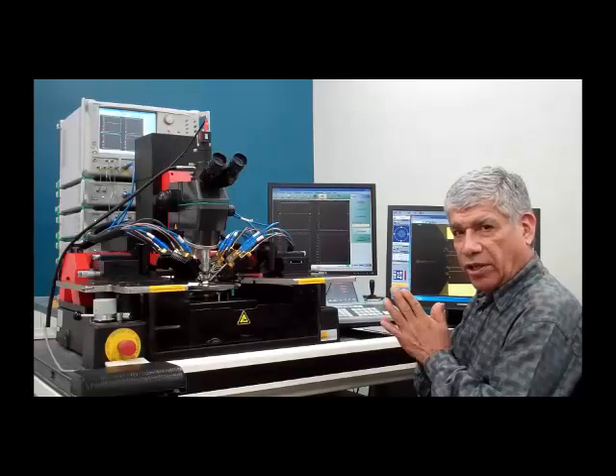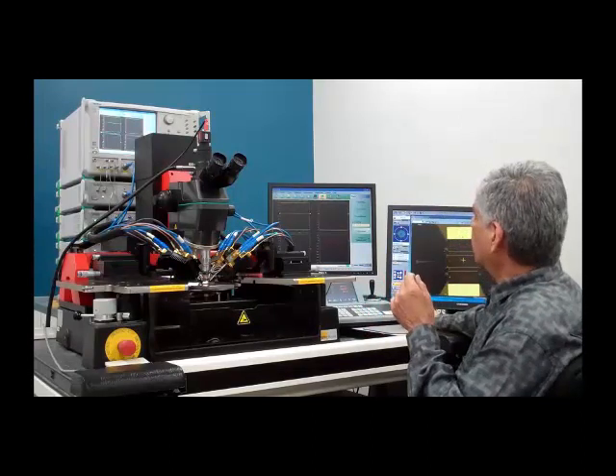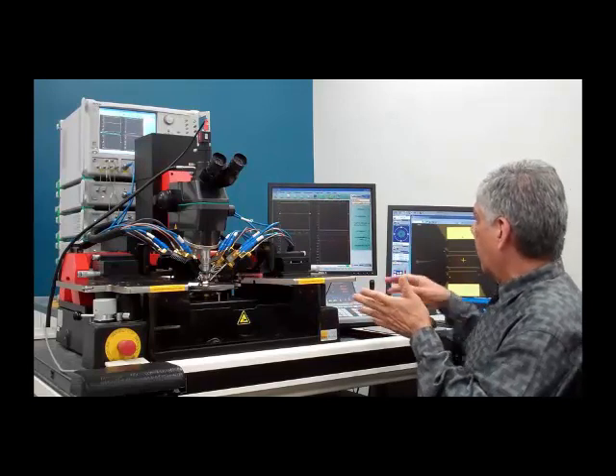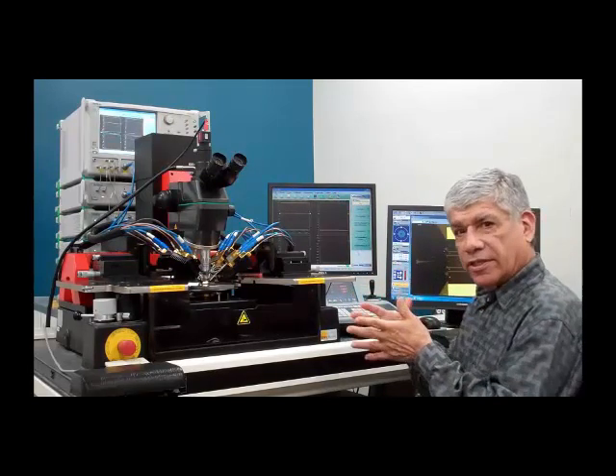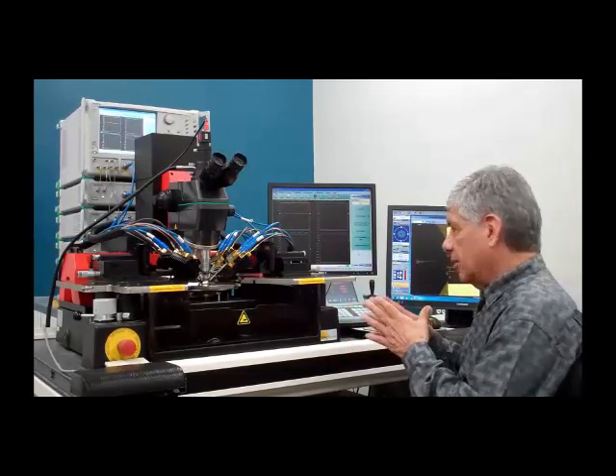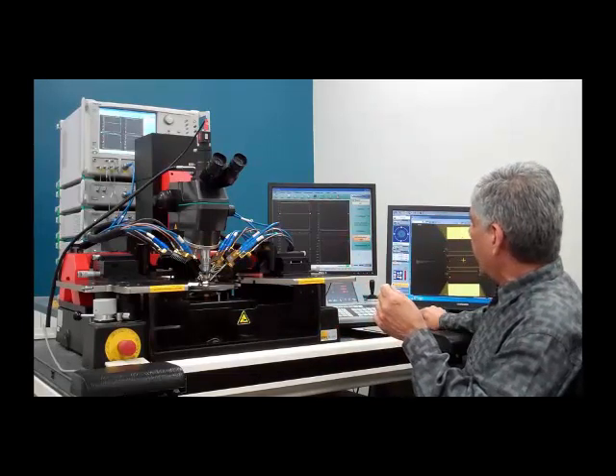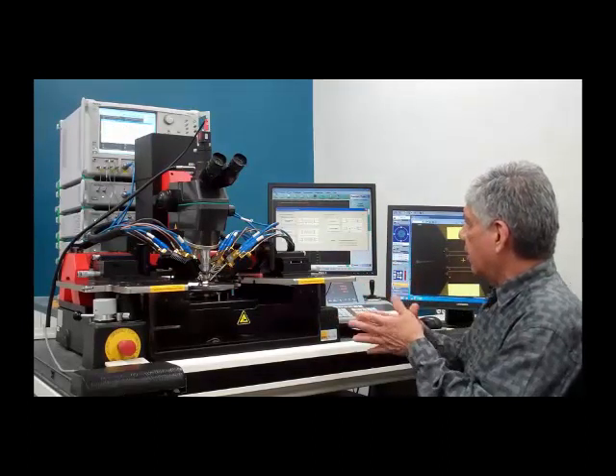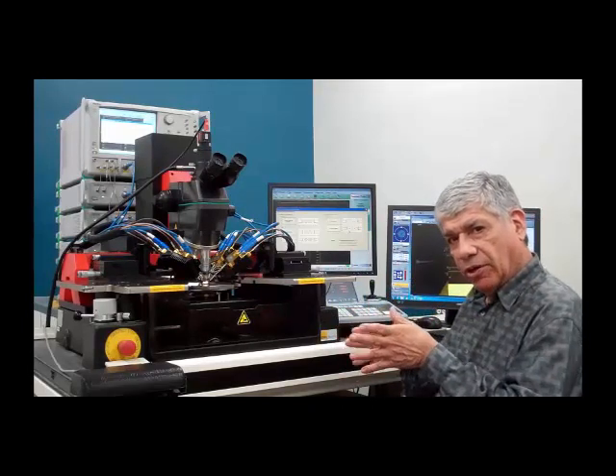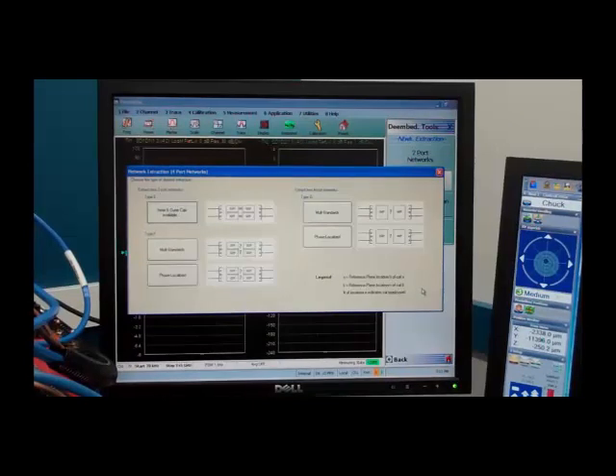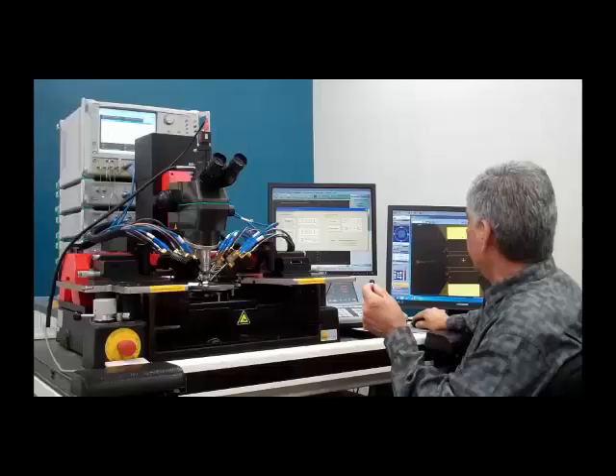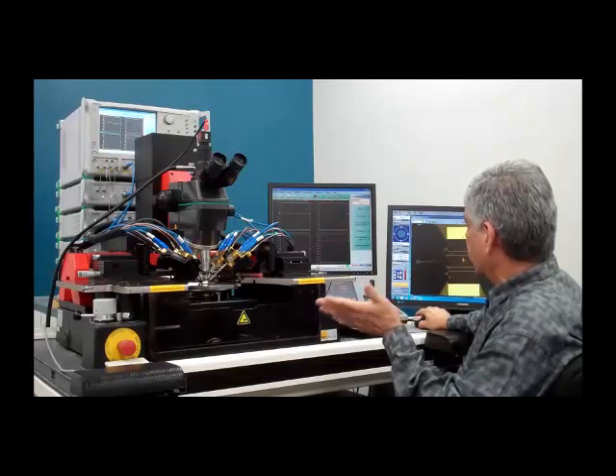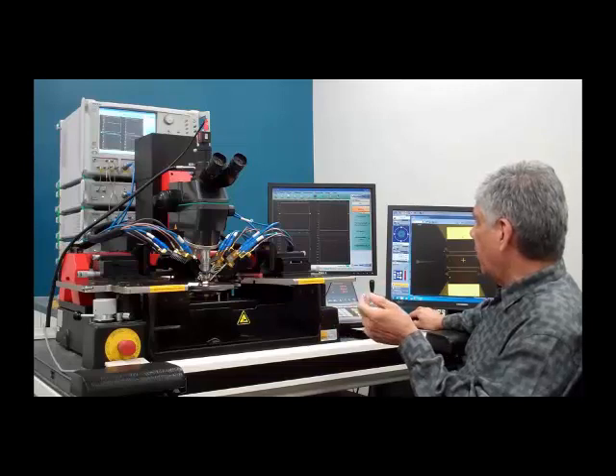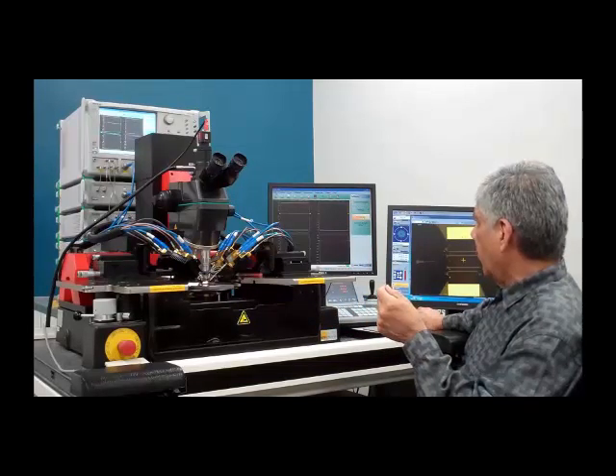So next, we're going to be doing a calibration, and first we do the setup for the calibration. So we go to our calibration menu, and here there are a number of other options and choices we have to configure the system for different types of calibrations, different types of de-embedding tools, etc. For instance, we have de-embedding tools for our 4-port devices. If you're using 4-port networks and you want to de-embed your test fixtures, you can go into the de-embedding routine and make measurements or do a calibration with those test fixtures and extract those out while you're doing your DUT measurements. So these are some of the things that are also available as part of the VectorStar system capability. So to do a calibration, then we go into our calibration mode, a manual calibration, 4-port.